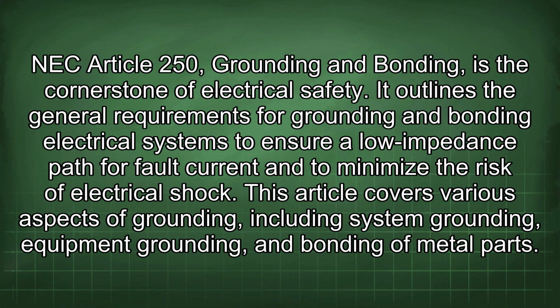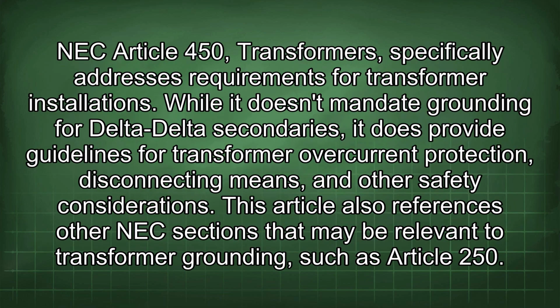This article covers various aspects of grounding, including system grounding, equipment grounding, and bonding of metal parts. NEC Article 450, Transformers, specifically addresses requirements for transformer installations. While it doesn't mandate grounding for delta-delta secondaries, it does provide guidelines for transformer overcurrent protection, disconnecting means, and other safety considerations. This article also references other NEC sections that may be relevant to transformer grounding, such as Article 250.